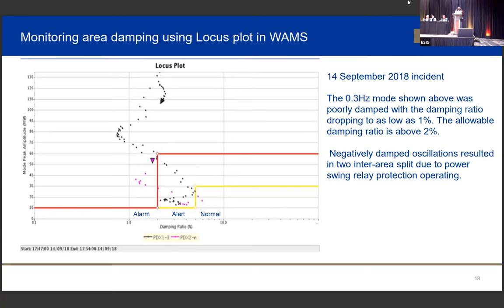And then again, we run the system within limits, because if we import a lot, then if there's a small disturbance, we tend to oscillate. So we make sure that we don't import or export a lot. We run within limits, especially transfer limits. So we have transfer limits for small signal. So is that mainly just based on past experience, which generator might be the cause of the issue? Yes. We also start offline studies, just to have the limits to say the controllers mustn't exceed the flow, and even frequency as well, because it affects a lot. Okay. Thank you.